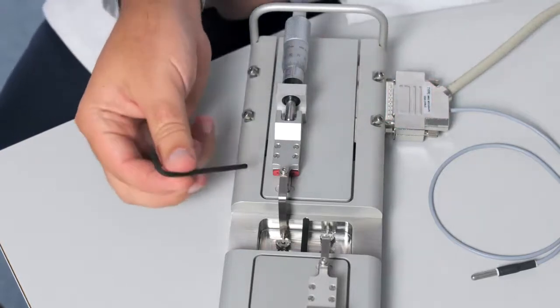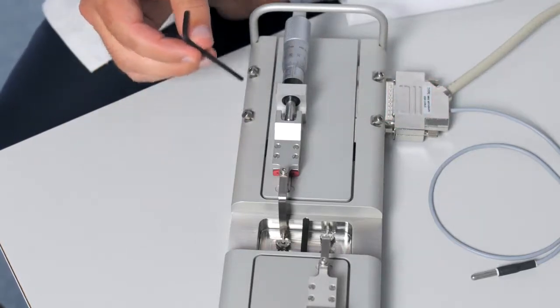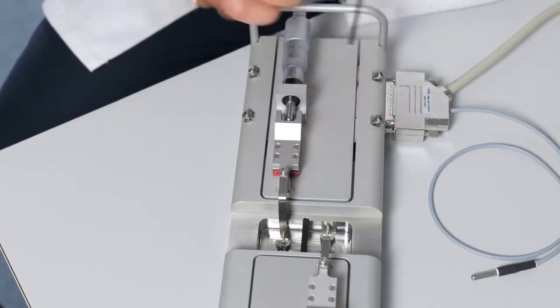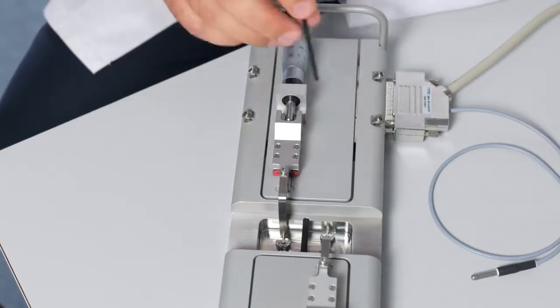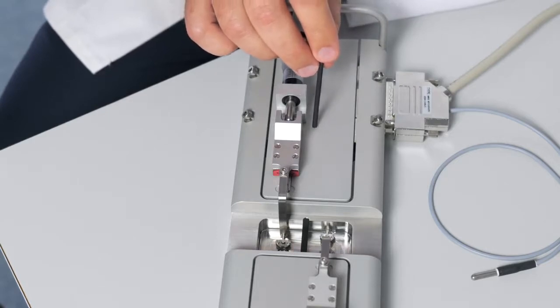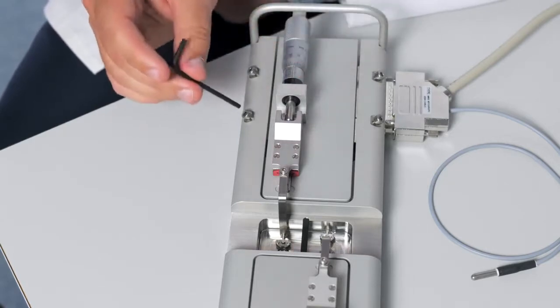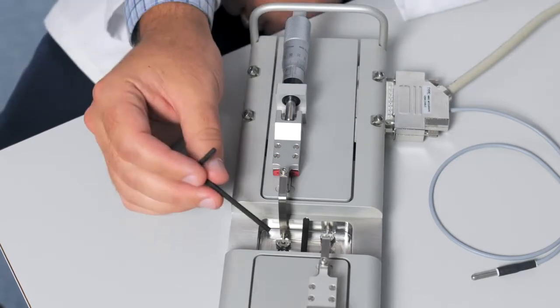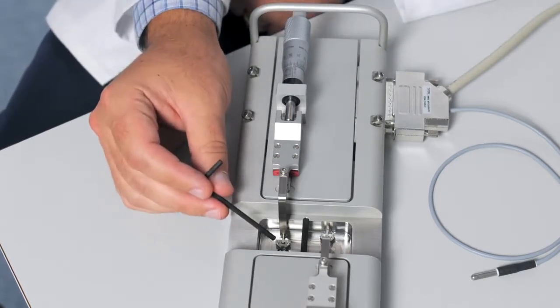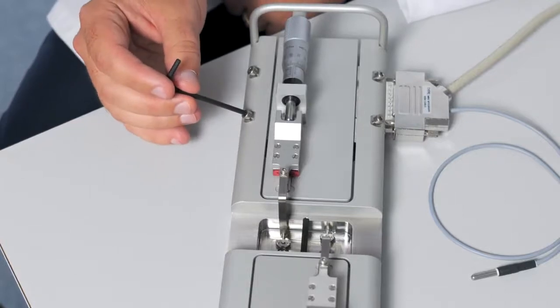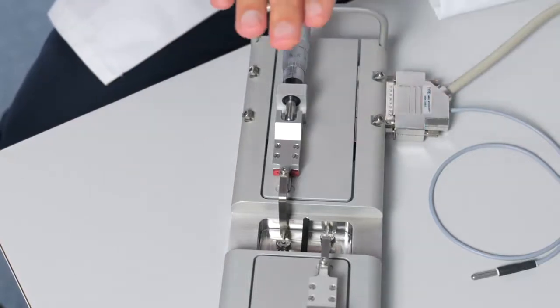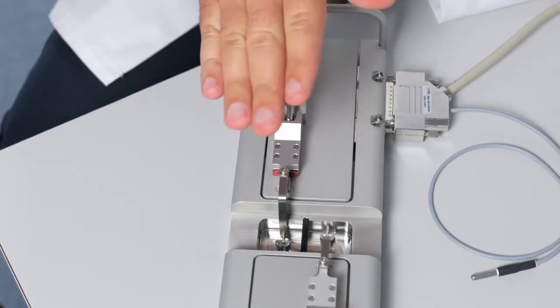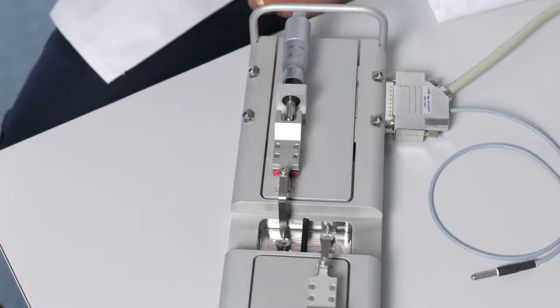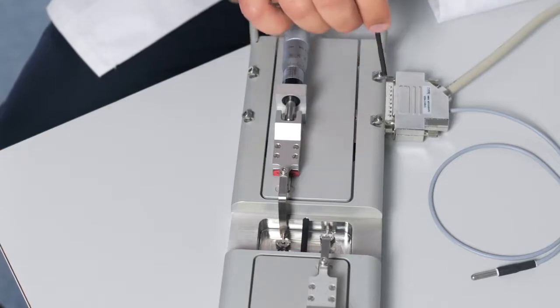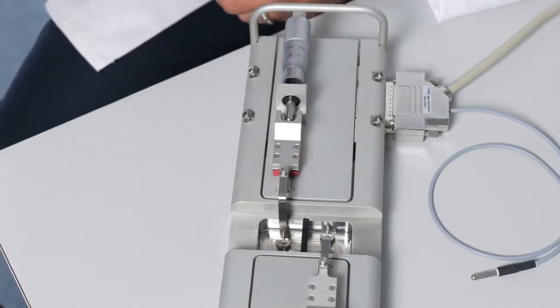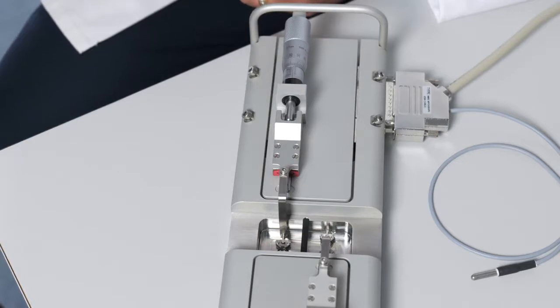Then you will use the Allen key to tighten or loosen the 4 positioner screws. In order to do this, visualize moving this plate when you tighten or loosen the screws, which will adjust the mount connected to this positioner. So if you were to tighten the front right screw, it would tilt the entire plate down and to the right. You will continue to make small adjustments with these 4 screws until your two sides match.